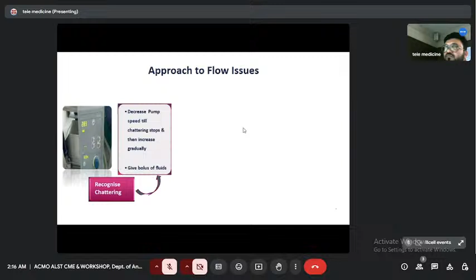Whenever chattering occurs, what do we have to do first? Decrease the pump flow. Why do we want to decrease the pump flow? Decrease it till the chattering stops. Otherwise, what happens? Usually flow issues are on the lower side, so we will increase the pump flow. What happens? More negative pressure. That will suck in more air. So there is a risk of air embolism also. So we have to decrease the pump speed till the chattering decreases.